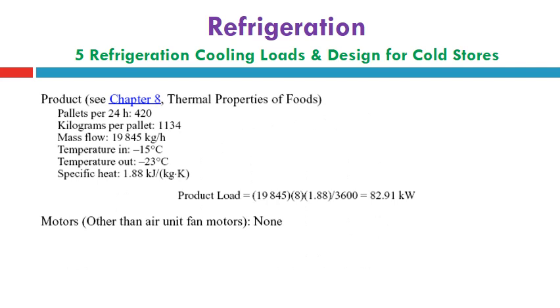Then the product load, he estimates the product load here in this slide by taking the temperature in and temperature out, -15 and -23, the difference is 8 degrees Celsius, and the specific heat he gets at 1.88, and the product mass flow, each pallet equal 19845 kilogram per hour. This is the mass flow. He estimates this mass flow according to the rate of the product that is listed in the heading of this problem, and finally he gets that the product load is equal to 82.91 kilowatt.